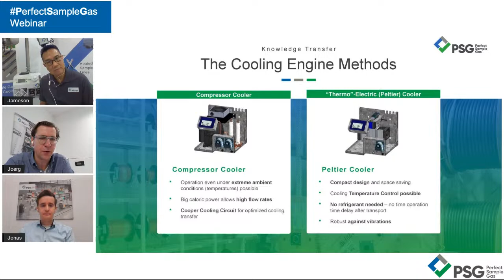So as we said, this gives a good overview of our different developed heat exchangers. On one hand we have the MLK 10 heat exchanger. Any comments, Jameson? I would say this heat exchanger is super robust. If you're unaware of the local situation, like you said, in many cases we don't know the flow rate or the inlet dew point, meaning the humidity coming in. What would you say, Jameson, maybe the MLK 10 is a good selection there?